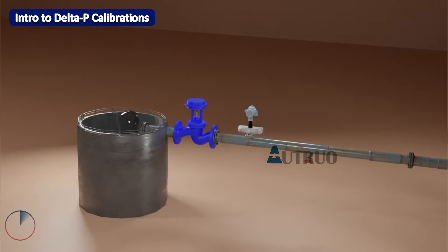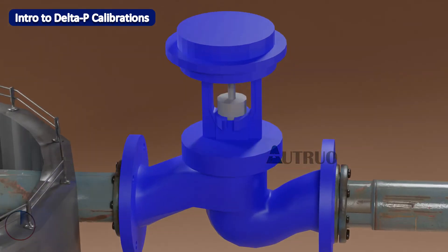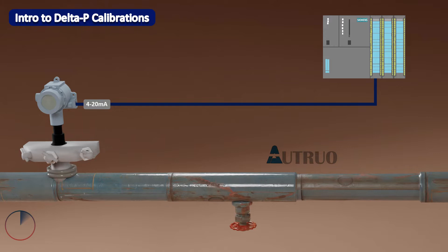So basically, we only need 1500 gallons for this product before the inlet valve closes. The volumetric flow rate of the fluid is converted to electric signals, and the signal will be sent to the PLC. The PLC will monitor the flowing signal coming from the transmitter, and decisions will be made when the preset values are attained.